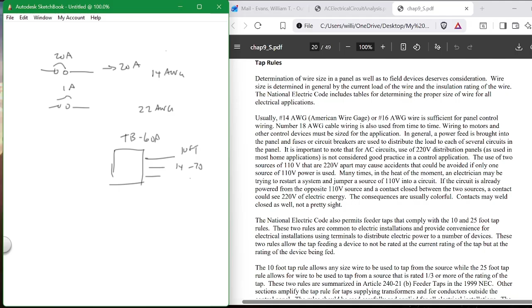However, in a control panel, you have what we call the 10-foot and a 25-foot tap rule, which says I can have a big terminal strip here, terminal block. It's a terminal block with places to land wires on, and this is like a 60 amp block. Let's say it's a 60 amp, but it's good for 60 amps. And I can have wires coming off of this and going 10 foot that are real little. I can put a 22 gauge wire off of the 60 amp and go 10 feet. If I go with a 14 gauge wire, which is good for 20 amps, I can go 25 feet.